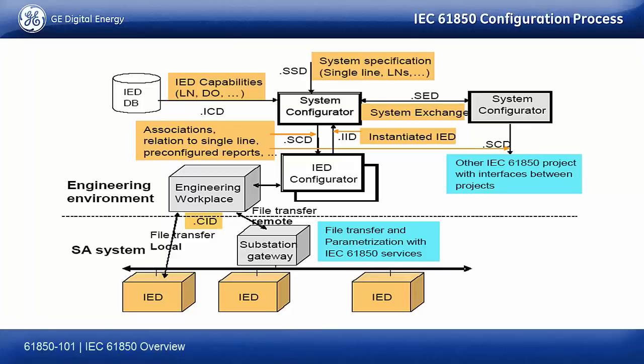Sounds great. Of course, to me, there's a huge challenge with that: the SCD file becomes the master of everything, and it defines the configuration or part of the configuration of all the devices in a substation. There are a lot of questions to me about how that file gets maintained, who owns the file, how every device becomes a touch point to that file, how it gets updated, maintained, and configured, and how different groups, like protection and automation, work simultaneously with the same stuff. How that really works out, right?